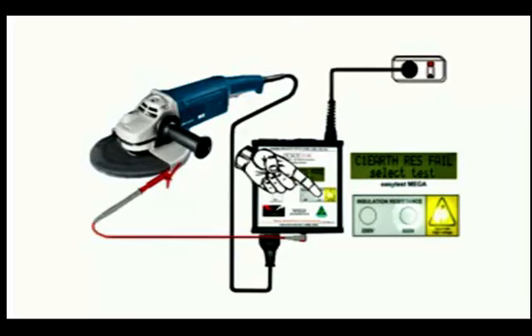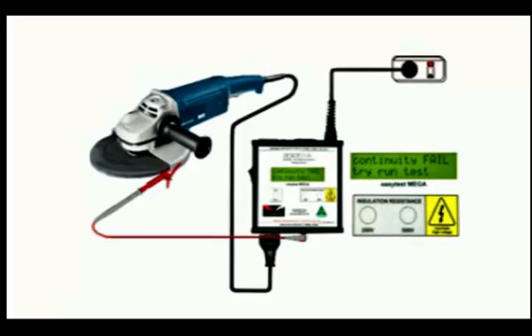Press the 500 volt button and the Mega first checks for continuity, that is, a complete circuit. In this case it's failed, suggesting a run test is needed. However, it's only because we've not switched on the tool. So close the switch on the tool and try again. Continuity is OK now, so the insulation is checked, and it passes. The test will automatically terminate in 30 seconds, or press the 500 volt button again to stop it now. Test completed. It really is that easy.